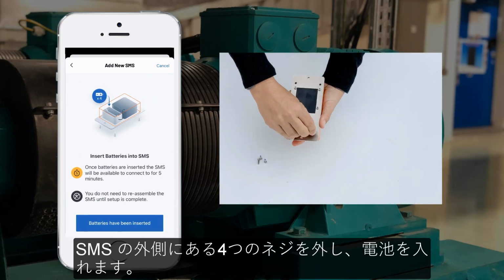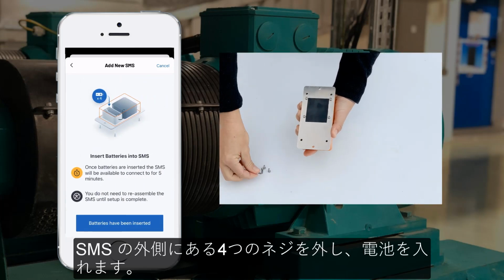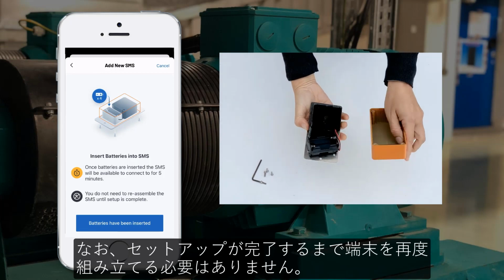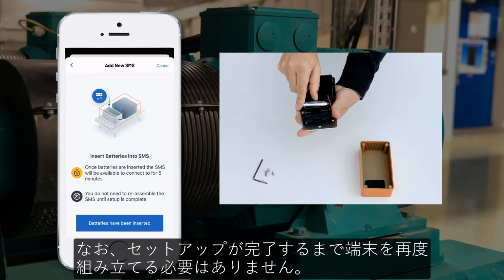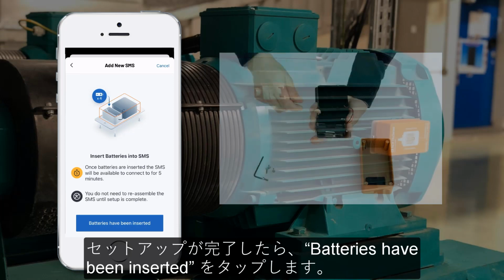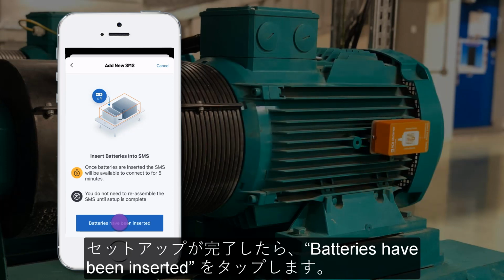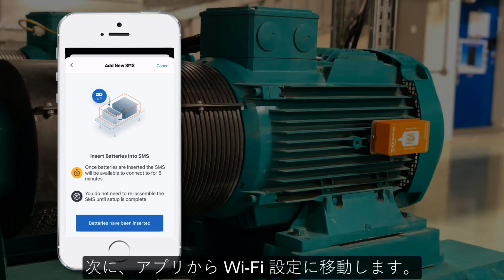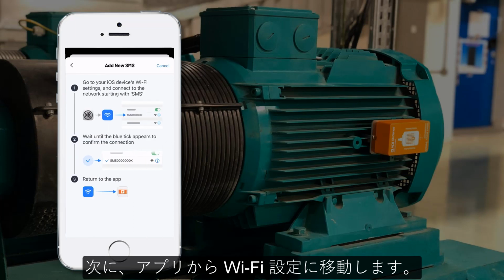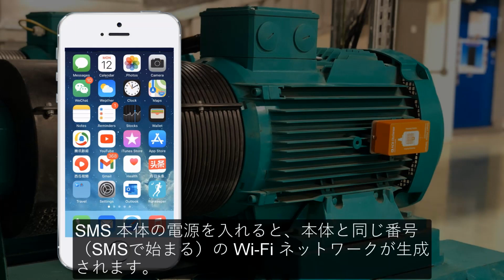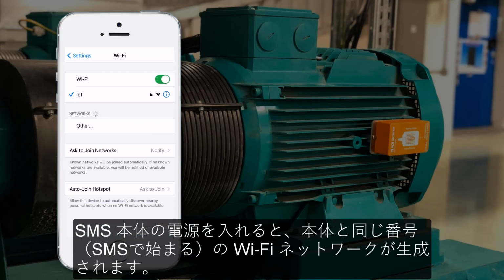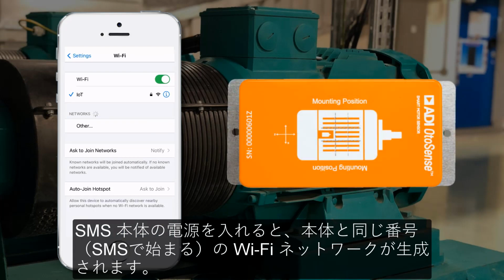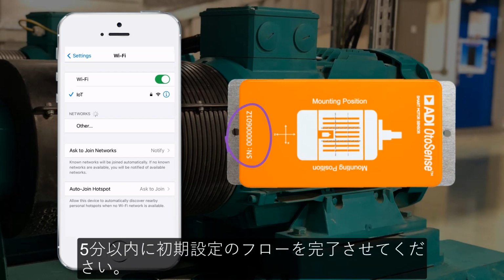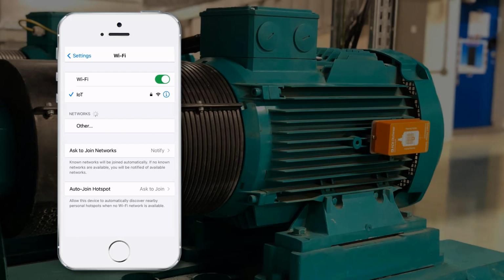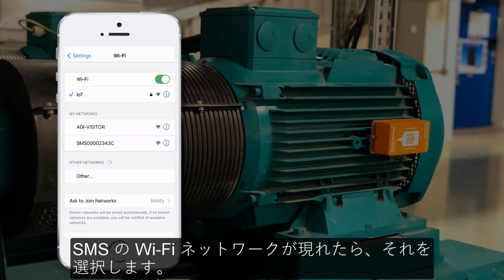Remove the four outer screws of the SMS device and insert the batteries. Note that you do not need to reassemble the device until the setup is complete. Once it's done, tap Batteries have been inserted. You now need to navigate out of the app and to the Wi-Fi settings. Powering up the device makes it generate a Wi-Fi network with the same numbering as the device, starting with the letters SMS. You will have 5 minutes to complete the commissioning flow. Wait for your SMS device to appear and select it.